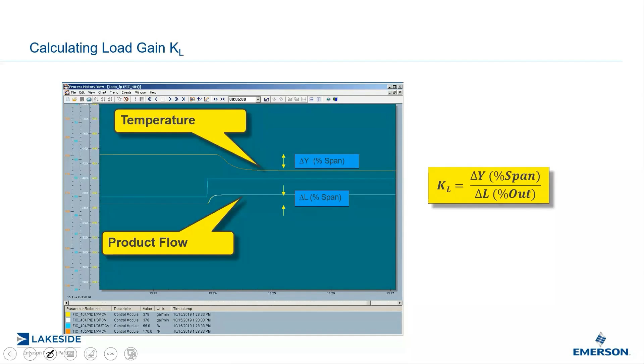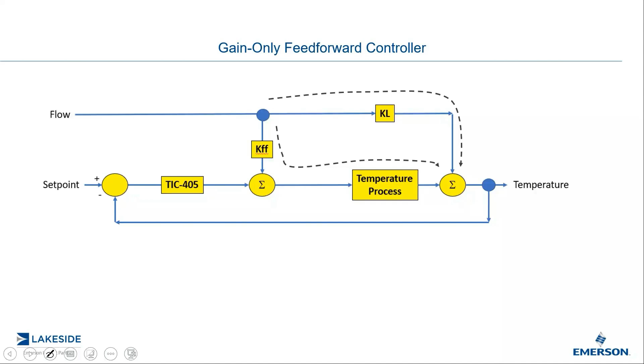So how does a feed-forward controller work? We know that every time there's a change in flow, it will affect the temperature. So we need to calculate the feed-forward gain, KFF, so that branch will cancel out the other branch, and therefore there should be no disturbance perceived by the PID controller.